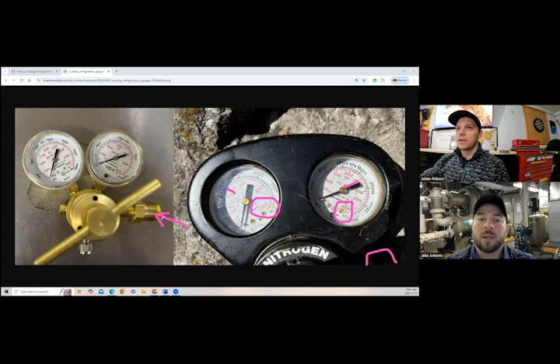Mm-hmm. All right. Yeah, the other thing to mention too, when you're working with gauges, the most accurate range is when the needle is vertical. When you're looking at a gauge, that's kind of the sweet spot that you want to look at, right? If you went all the way over to the 1,000 psi mark there, you're going to be kind of way out of the scale. So on both of these, when they're at their maximum capacities, they're going to be mostly in that middle range. So you can see why that makes sense, right? Good. So what Jake is saying for everybody that's on the visual, between 0 and 1,000 is going to be 500 psi. So if your needle is here, that's going to be an accurate range to use the regulator within.